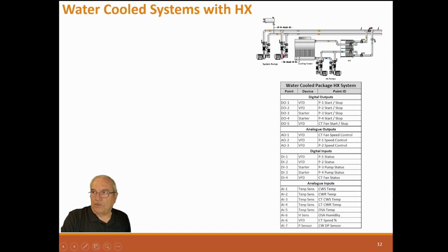Digital inputs: VFD pump 1, VFD pump 2 status. These two are VFD statuses. P3 pump status, these are just starters. P4 is a starter, and DI5 is the fan status off the VFD, off the fluid cooler. Analog inputs: condenser water supply, condenser water return temperatures. So now we have temperature sensors here for the system, and we have temperature sensors here for the cooling tower. So we have analog input 1, condenser water supply temperature, condenser water return temperature, which is these out here. Then we have cooling tower condenser water supply and return, which is these two here. And then we have outside air temperature, outside air humidity. We have the VFD speed off the fan, and we have a differential pressure sensor out of the system to run these VFDs. So that's the standard for that.